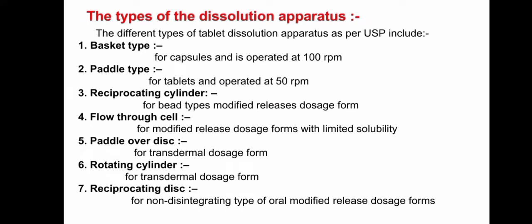The types of dissolution apparatus. The different types of tablet dissolution apparatus as per USP include: 1. Basket type for capsules, operated at 100 RPM. 2. Paddle type for tablets, operated at 50 RPM.